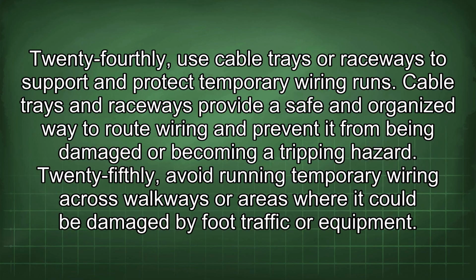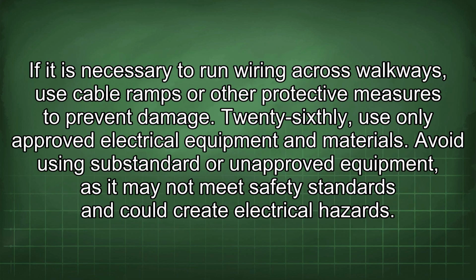24thly, use cable trays or raceways to support and protect temporary wiring runs. Cable trays and raceways provide a safe and organized way to route wiring and prevent it from being damaged or becoming a tripping hazard. 25thly, avoid running temporary wiring across walkways or areas where it could be damaged by foot traffic or equipment. If it is necessary to run wiring across walkways, use cable ramps or other protective measures to prevent damage. 26thly, use only approved electrical equipment and materials.